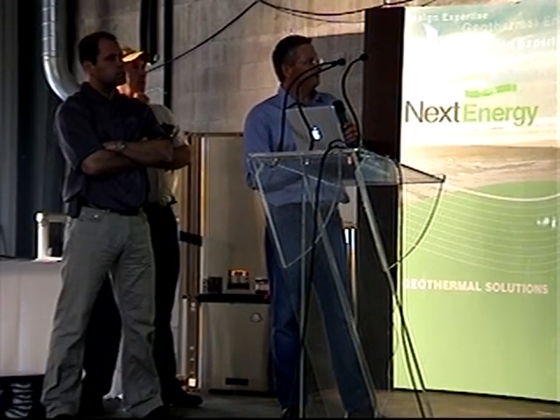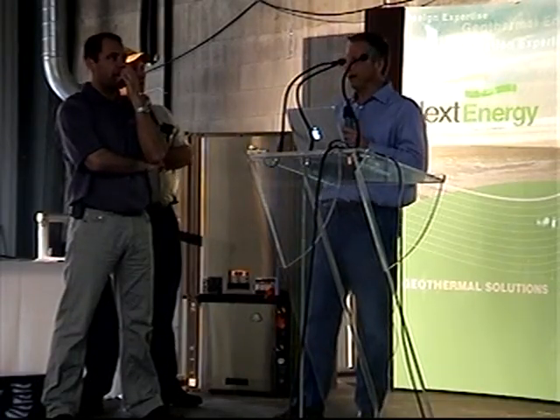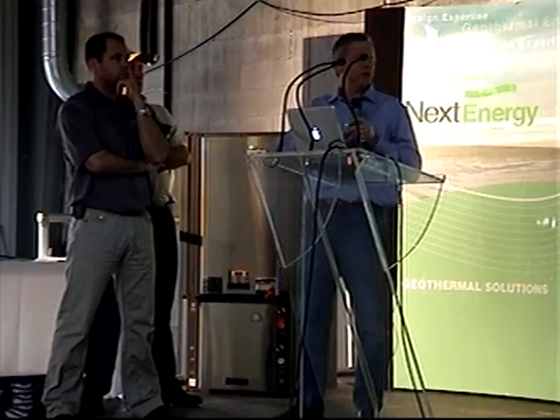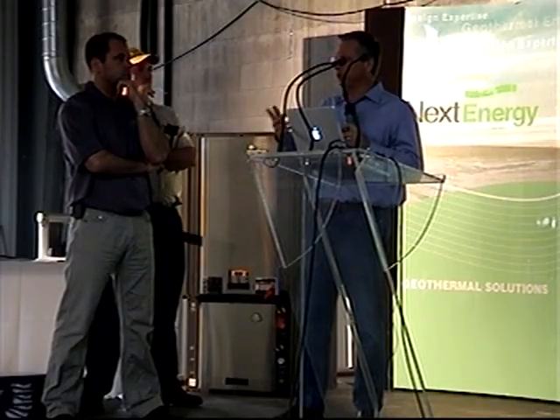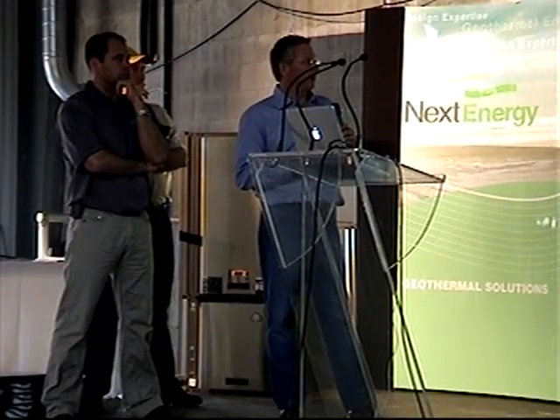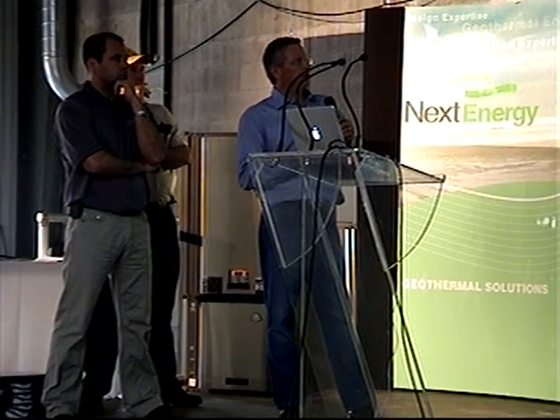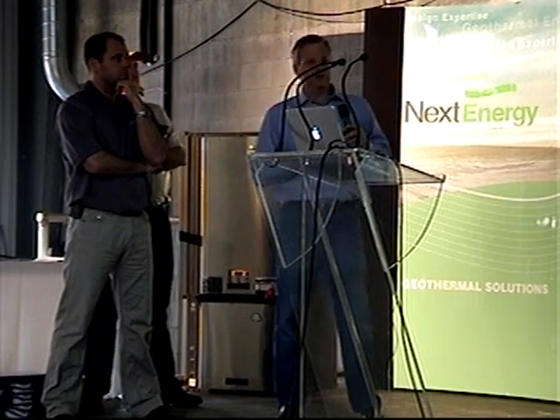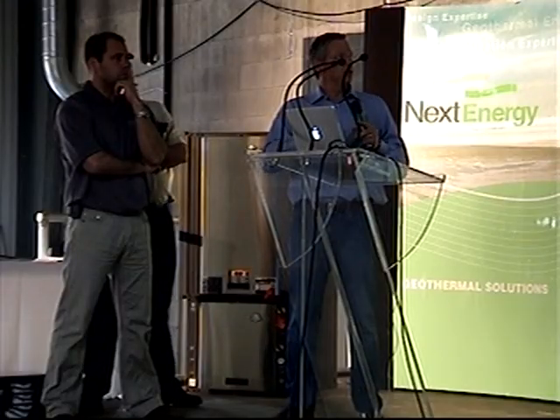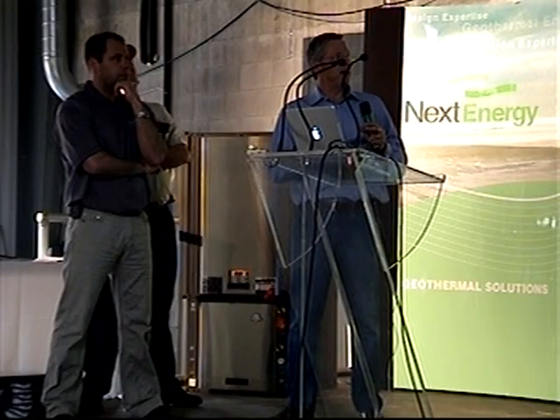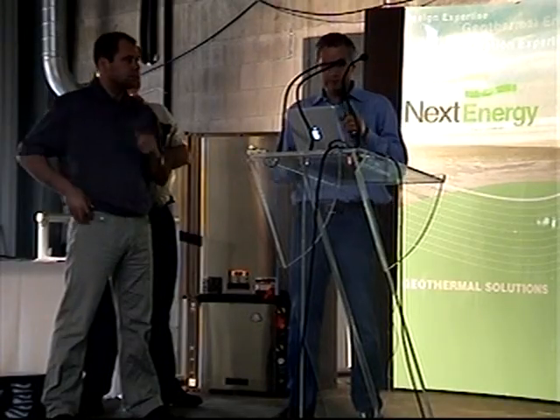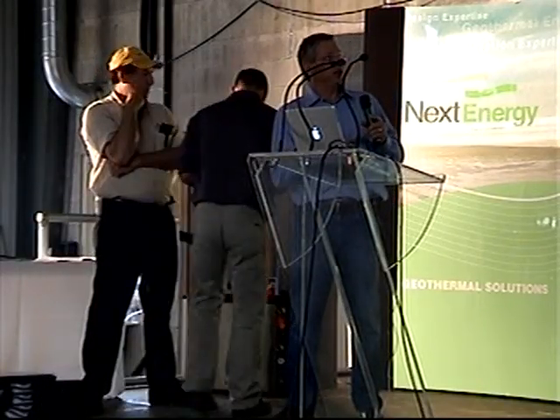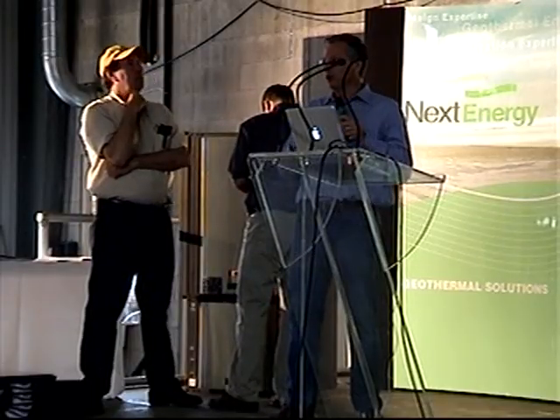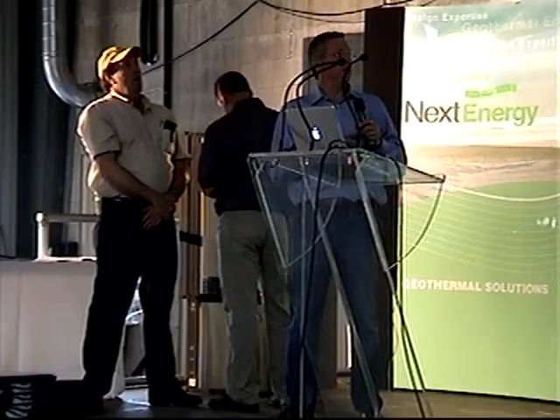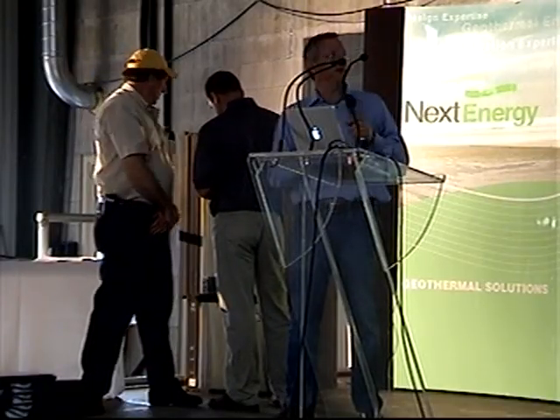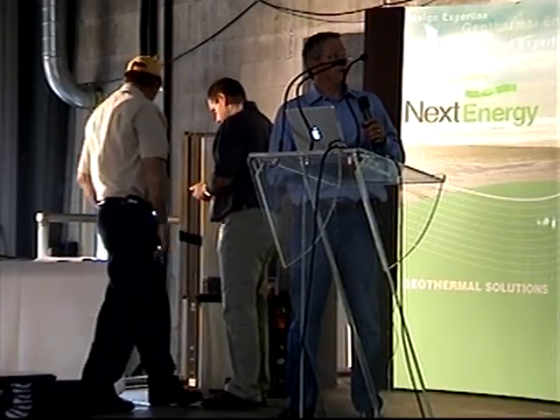There's anti-short cycle, so you can't short cycle the compressor. You might say, wow, it's good overall, but it can be frustrating at times. But we got a way to speed that up if you're working on the unit and pretty well knock that out of your way. We have air coil freeze protection and water coil freeze protection. There's basically the same sensors providing this, monitoring the evaporating temperature and the condensing temperature in either direction. But essentially, in this mode, it's looking and saying if the air coil freezes up during cooling, then it'll shut the unit off, lock out. If the water coil freezes up, it shuts the unit off, locks out, or just before it freezes up.